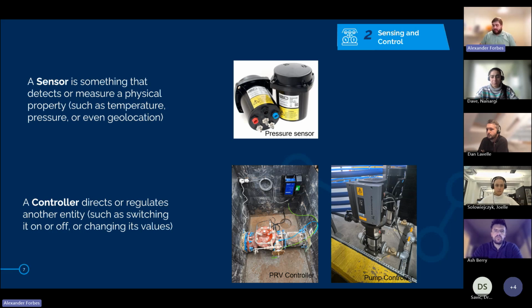So in this case I've got 2 examples. The one on the left is a PRV controller, you can see it attached to the wall there. The PRV itself is able to actuate, because it's a PRV it will do what PRVs do, but the controller is able to tweak that control and make it operate more effectively, more efficiently, maybe even change the set point depending on the situation the network finds itself in.